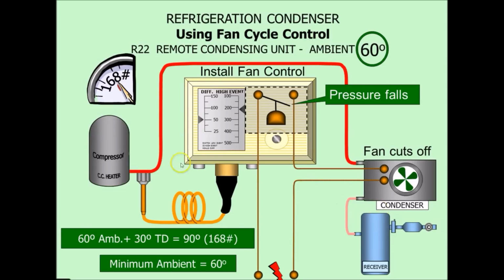So once you get the pressure port installed, you're going to locate the L1 terminal to the condenser fan and break that wiring, and you'll wire it into the pressure switch controls.